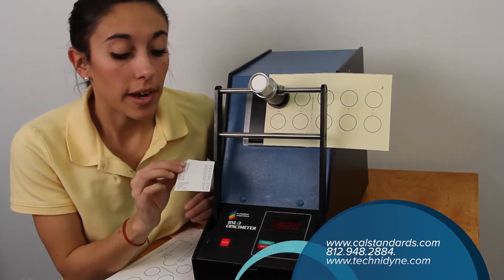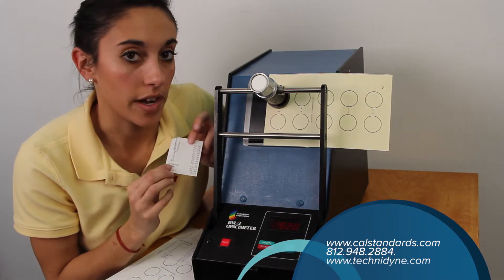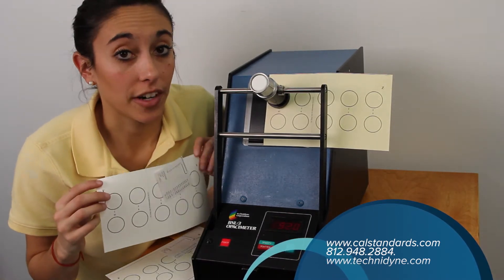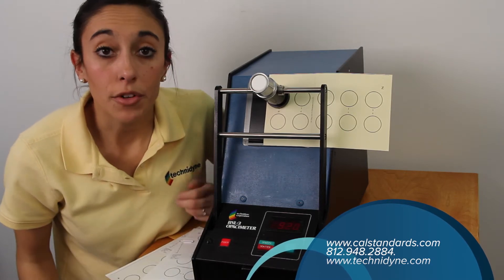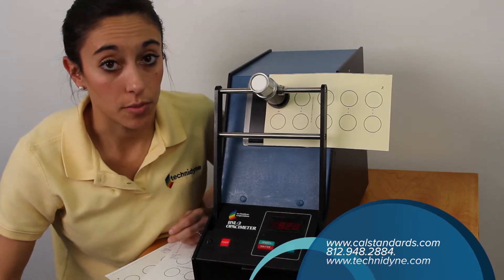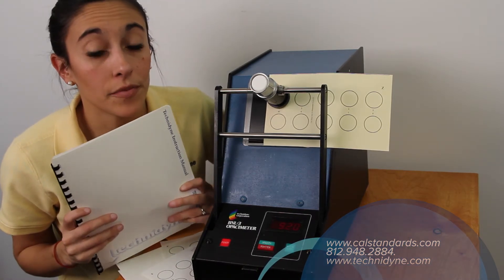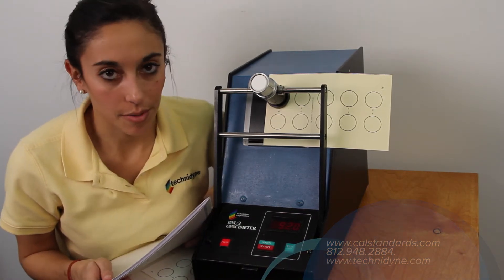That average should be within plus or minus 0.3 of the average from your printout. Follow those same steps for the last two paper verification standards — those averages should be within plus or minus 0.3 as well. If they're not, or if you have any other questions, you can refer to your Technidyne operator's manual, call Technidyne, or check out the website.